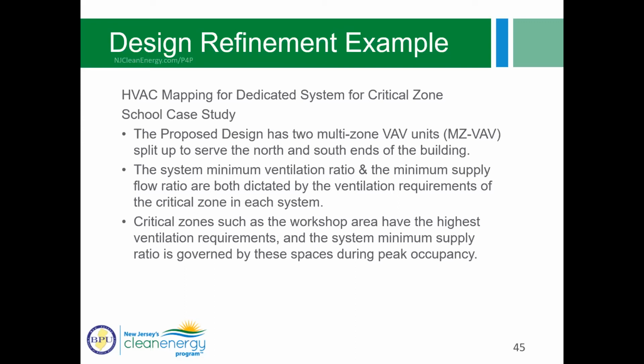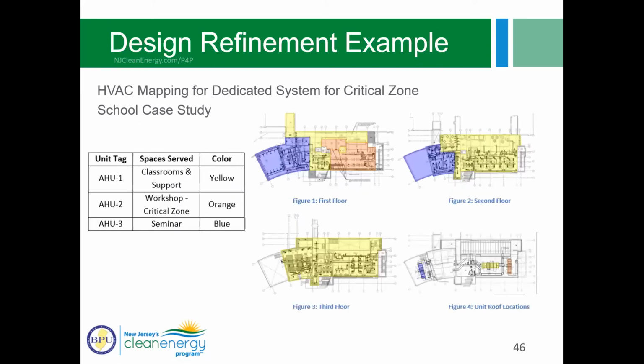And this is not optimized. So what can you do? Well, in this scenario, what you can do, and what this is showing here, is basically you can give that workshop, that critical zone, its own variable volume single zone unit. And so that single zone unit will operate, and it will meet the high demand for outside air required by that workshop. And so that zone is now not part of that original multi-zone variable air volume system. And now that multi-zone system can operate at a lower supply ratio because it's not being governed by that critical zone anymore.